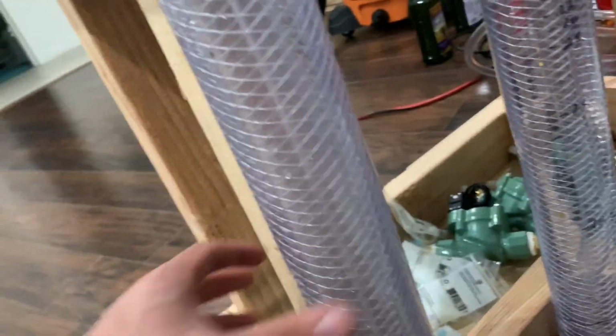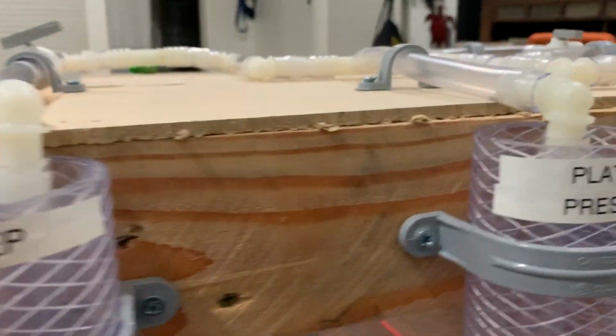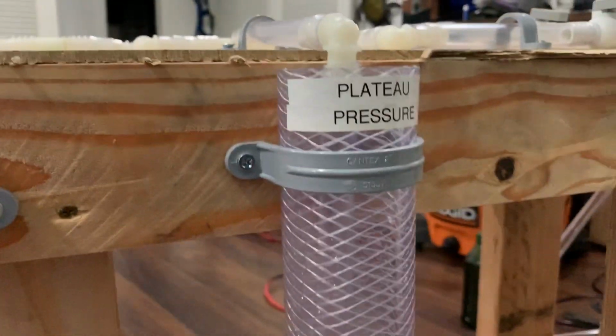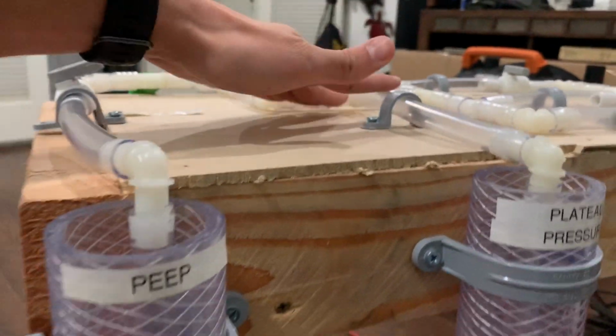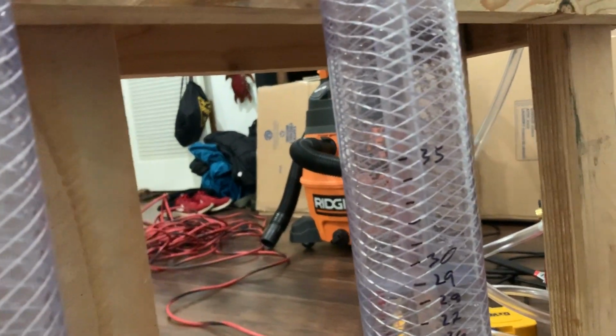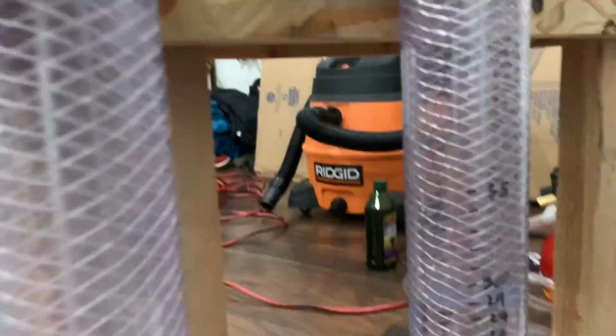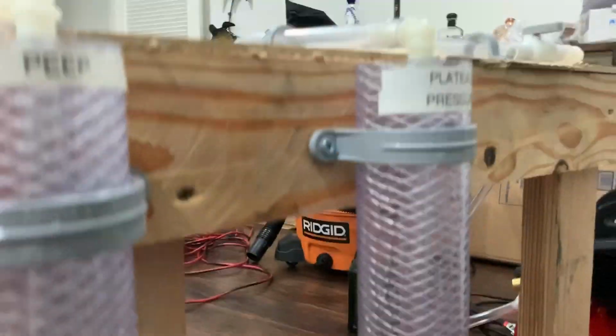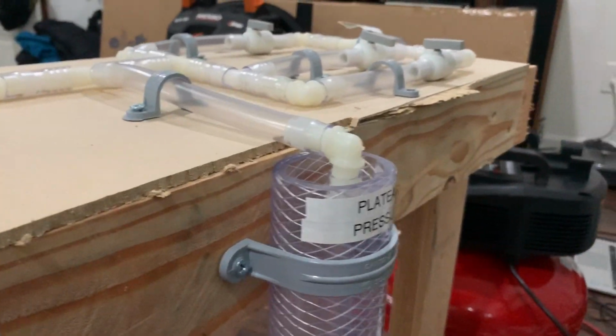So now let's take a look at the 2 pressure controllers that we have. You can see this one is labeled PEEP, and this one is labeled plateau pressure. The one labeled plateau pressure comes from the inspiratory side, and you can see that there's a water column in here, quite literally filled. Right now it looks like it's right below 29, and that's 29 centimeters of water, meaning that if you go above 29 centimeters of water pressure in any of this tubing, then that will actually bubble through here, and that will prevent you from causing barotrauma, or in our case, popping the balloon.